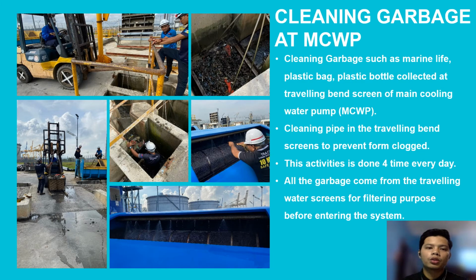So this is one of my training activities at this plant. Cleaning garbage at main cooling water pump, or we call as MCWP. During sucking the seawater, garbage will follow along the process. This seawater is used to cooling the condenser in this power plant. This garbage such as marine life such as kupang, udang, ikan and plastic waste to be filtered from entering the system. This is because the garbage will bring harm to the system. This activity will be done 4 times per day.